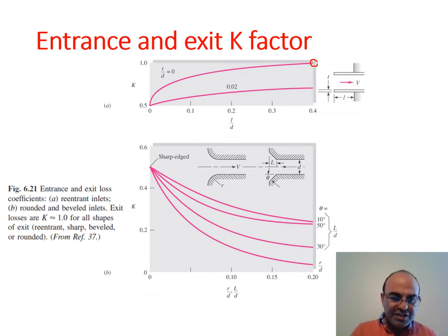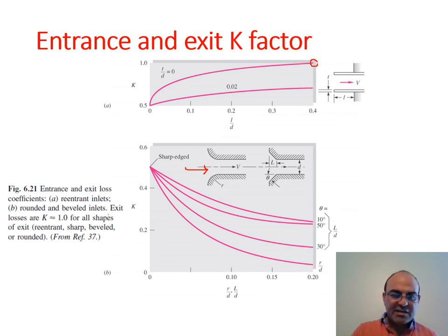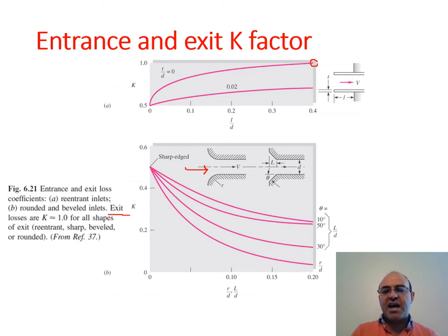In part (b), rounded and beveled inlets are shown. The flow goes left to right, and K can be estimated as a function of r/D, L/D, and the bevel angle theta. For exit losses, K ≈ 1 for all shapes of exit — because the velocity head is essentially lost at the exit and cannot be recovered.